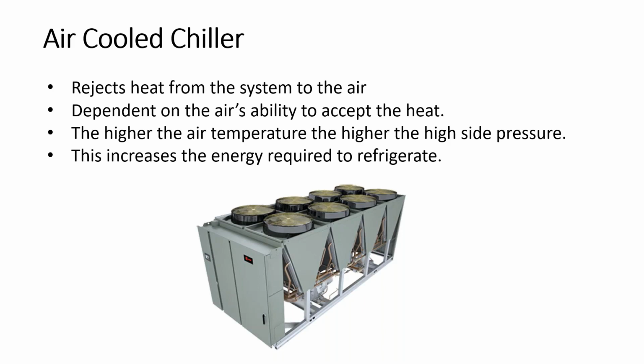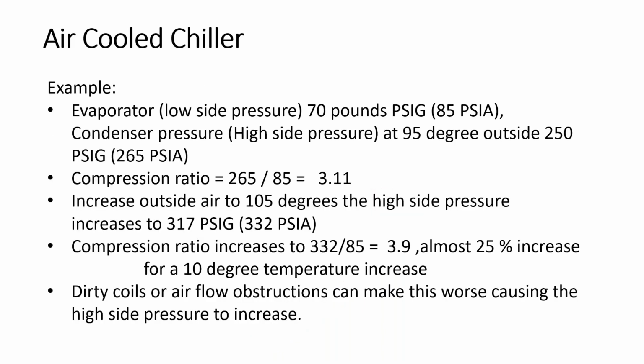It increases the energy. That's one of the things we're going to talk about, and we'll do an example to give you an idea of what's happening. For example, we've got a 70-pound low side on the evaporator at about 85 psi. Then condenser pressure at 95 degrees outside runs about 250 or 265 psi. The compression ratio, you just do simple math, is about 3.11. Now, we go from 95 to 105 outside. Your high side pressure increases to 332 psi. And you do the math again, you're still trying to maintain the low side at the same temperature because you're trying to produce chilled water. But your compression ratio is increased to 3.9. That's almost a 25% increase for a 10-degree temperature increase.